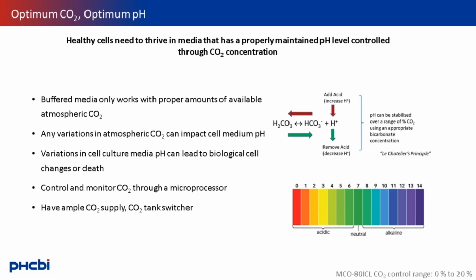Healthy cells rely on proper amounts of atmospheric CO2 to be readily available. Cell media depends on the delicate balance of dissolved carbon dioxide and bicarbonate to maintain proper pH levels for healthy cell growth. Changes in the atmospheric CO2 can alter the pH of the medium and cause detrimental changes to the cell culture, including death. It's important that every cubic inch of the incubator chamber is saturated with proper levels of carbon dioxide, most often 5%, to ensure CO2 is at the proper levels and it stays there.